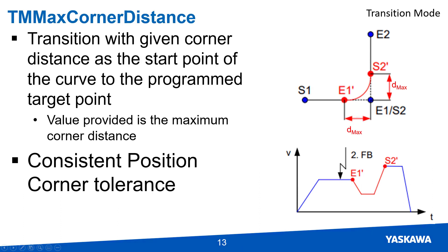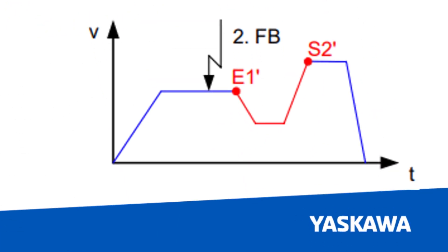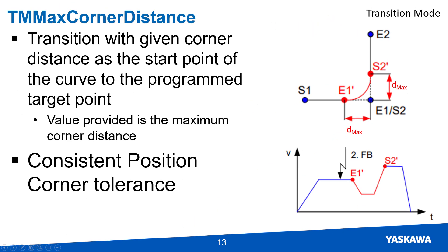The TM Max Corner Distance transition builds upon TM Corner Distance mode. Instead of defining a hard start point d, the user defines a max position d-max from the next segment's starting point. The controller will try to get as close to the corner while keeping the current velocity without exceeding the acceleration and max distance constraints. If the transition would exceed the max distance specified, the velocity would need to be adjusted to stay within the transition distance parameter. This mode allows the user to keep the transitions within a certain position tolerance.